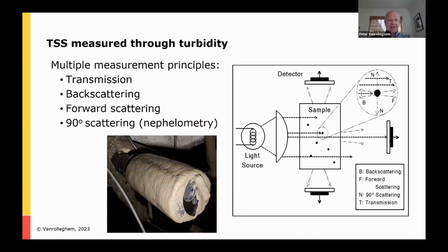This is a nephelometer, a Solitax. You see the light emitter and the receiver, and it's on 90 degrees, and you see that these systems are subject to quite some pollution. This is the treatment plant in Quebec, where we have alum, which is added to the drinking water that ends up in the sewer system and then leads to this type of problem. Luckily, there are wipers that keep the lenses clean, reasonably clean.